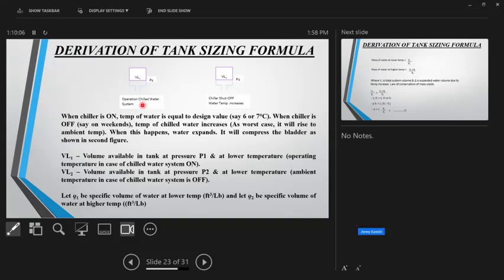Yes, before proceeding to the next slide, I just want a clarification on this. You said that based on the unit's chilled water off and on conditions, this volume will be varying and the pressure in the tank will be varying. But in the previous slides, you mentioned that the expansion tank pressure before the pump and after the pump will be constant. How can we justify that? The word I used was that the pressure in the expansion tank is constant when the temperature is constant.